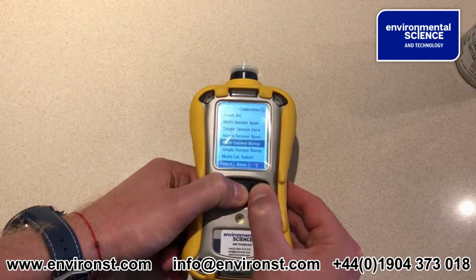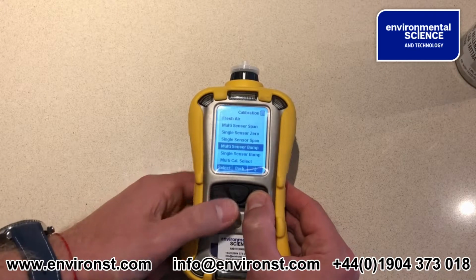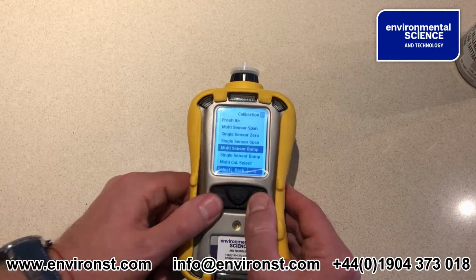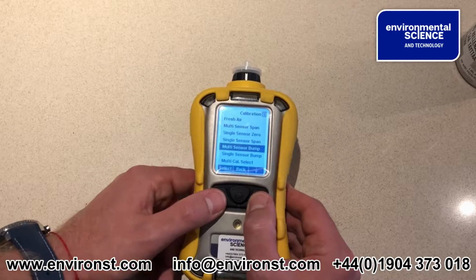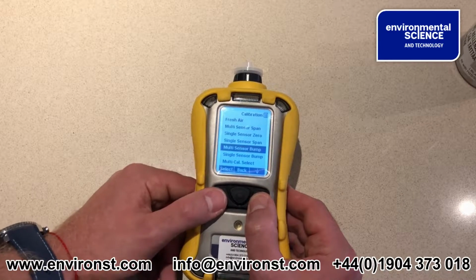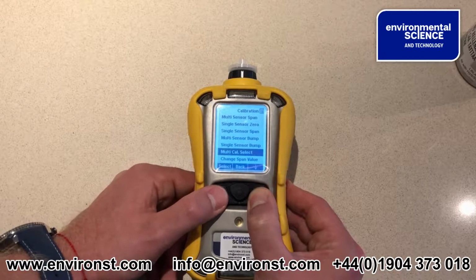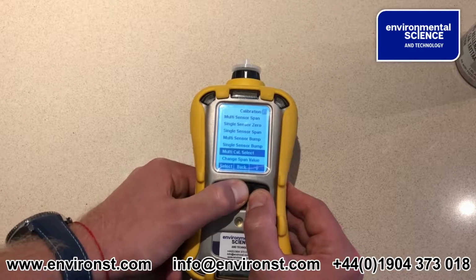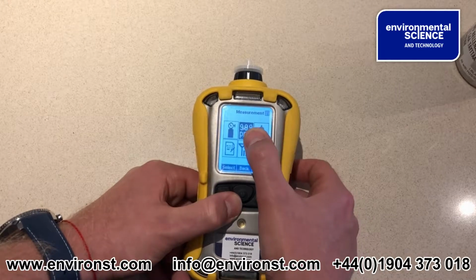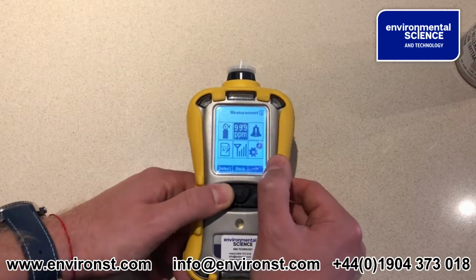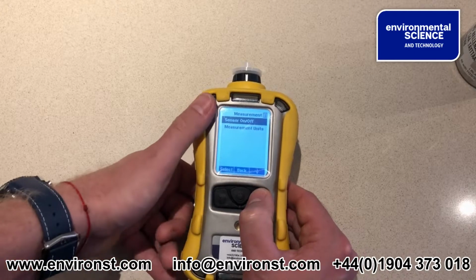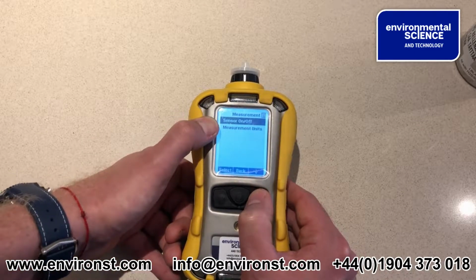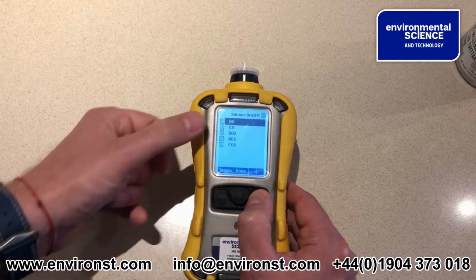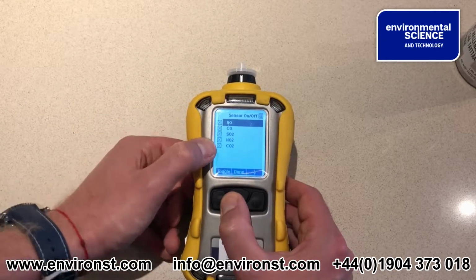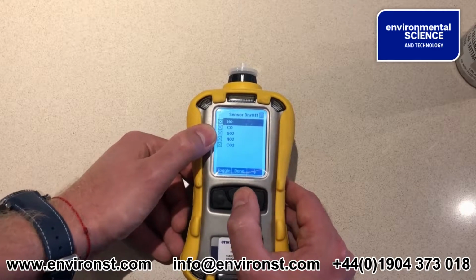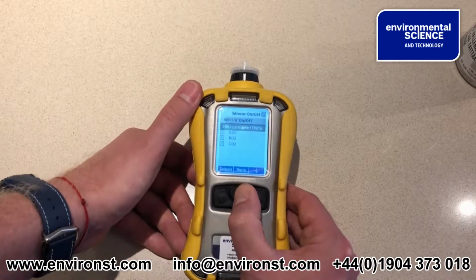Now we're not going to show you single sensor bumps and all that sort of thing. If you want to do it, you can do, but it's literally just checks to see if sensors are working properly rather than actually calibrating them. So that's all we're going to show you from the calibration menu. If we go to the 999 ppm, which basically is the measurement units menu, you'll see that we can turn sensors on and off and change the measurement units. So if I select this, I can essentially toggle which sensors are turned on and off here. Now I'm not going to do that because I don't need to, but the option's there for you.